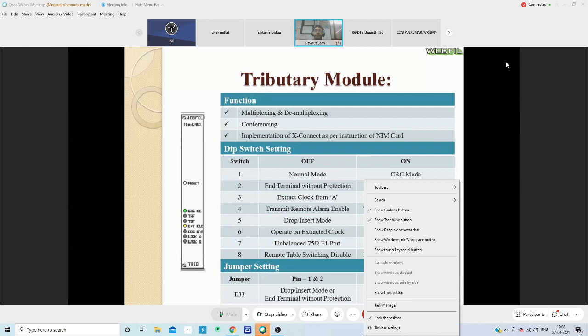Now the final dip switch number 8, as I discussed before, decides whether remote table switching will be enabled or disabled. In the end stations, this remote table switching needs to be enabled. So in both end stations, dip switch number 8 needs to be kept on. In all intermediate stations, dip switch number 8 needs to be kept off.